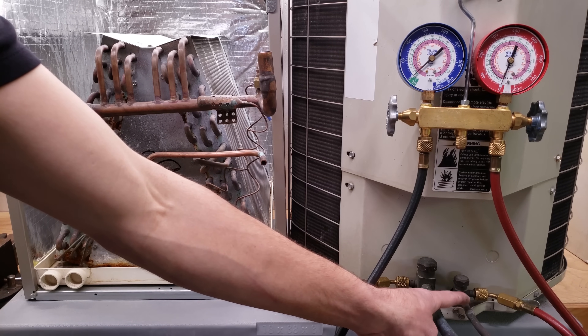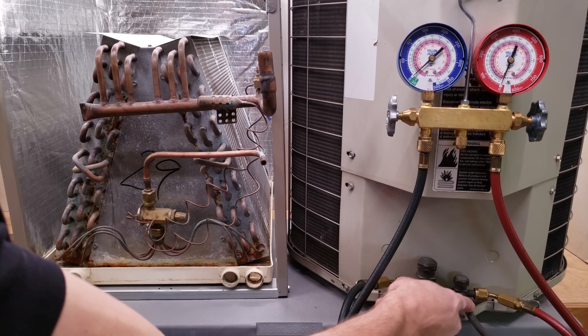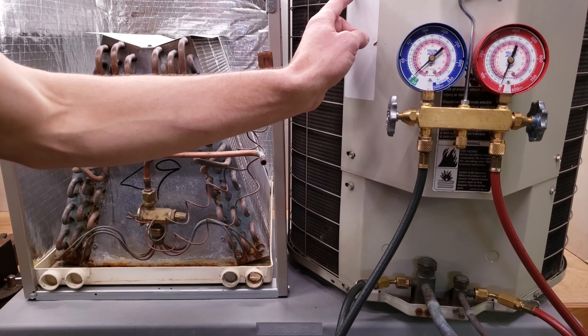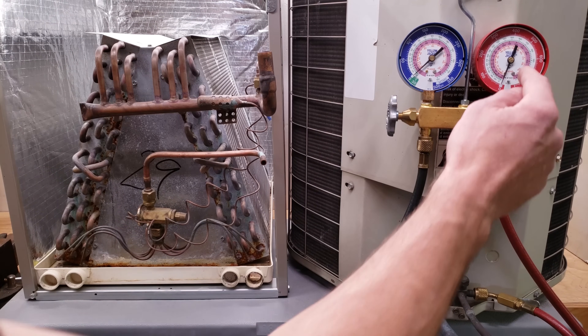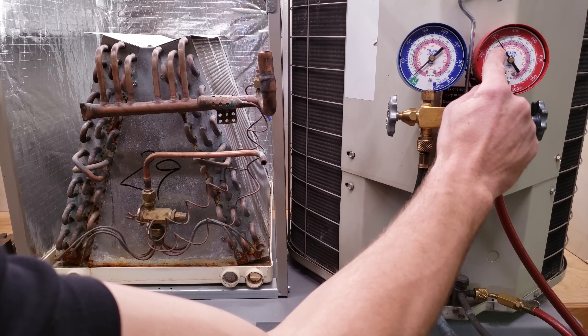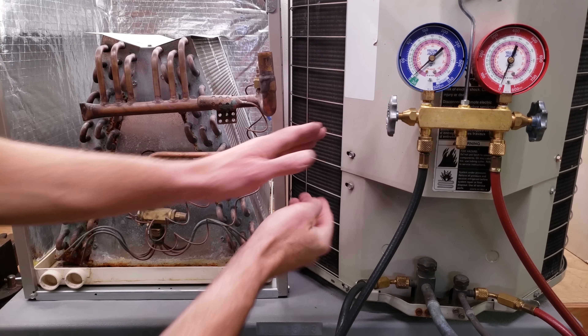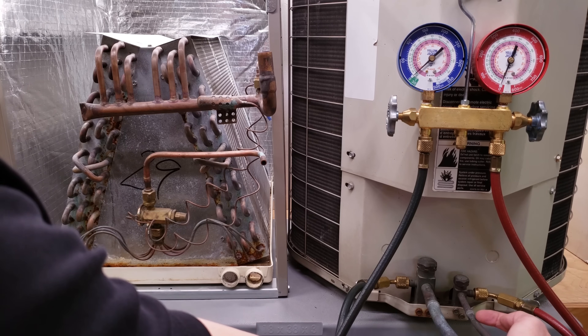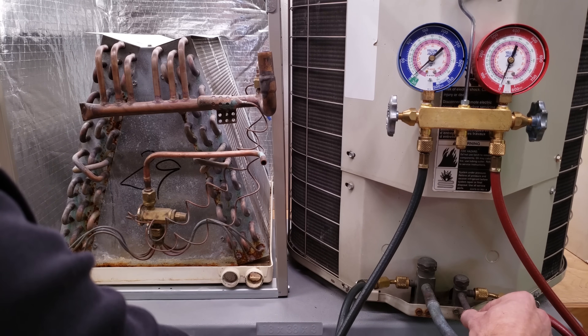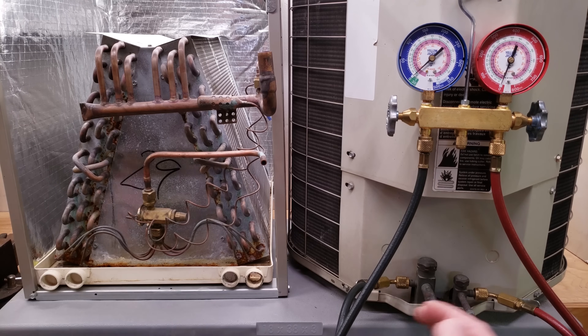Then you take a digital temperature reading on the outside of this liquid tube. The temperature on this liquid tube will be lower than the saturated temperature you converted the pressure to. For example, if this unit is R410A and you measured a pressure on the liquid line of 300 psi while the system was running, that converts to a saturated temperature of 94 degrees. Then you take an actual temperature measurement right here on the liquid line within a few inches of the port. If you measured 84 degrees on the line, that's 94 degrees saturated temperature minus 84 degrees actual line temperature — that's 10 degrees of subcooling.